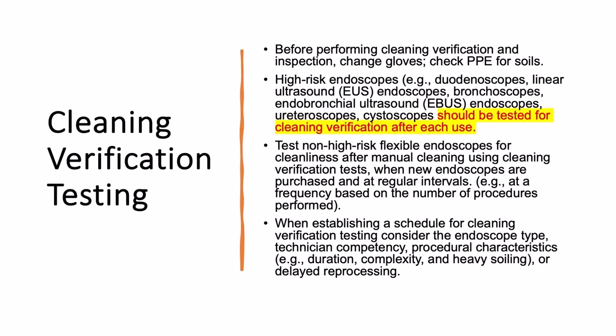Test non-high-risk flexible endoscopes for cleanliness after manual cleaning using your cleaning verification test when new endoscopes are purchased and at regular intervals. Now, they put the frequency based on the number of procedures performed. I have to tell you that, in my opinion, why would you proceed with high-level disinfection or sterilization of a scope if you weren't sure that it was clean? In my opinion, we should be testing every single scope. That's the standard of care that I would want for a scope used on me. But this is something you get your committee together, your multidisciplinary team, and come up with a schedule.